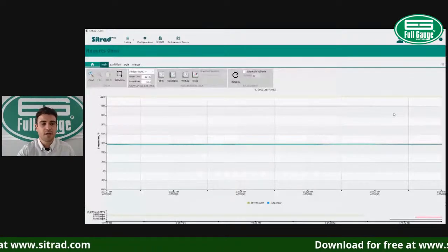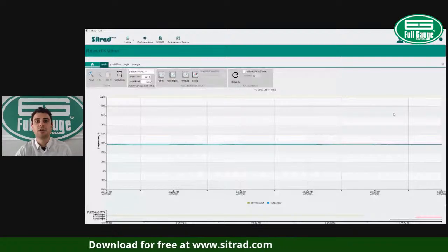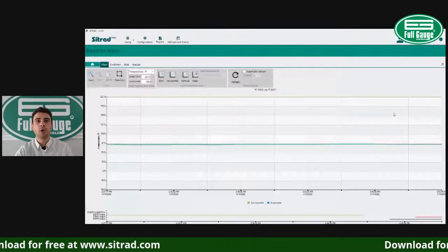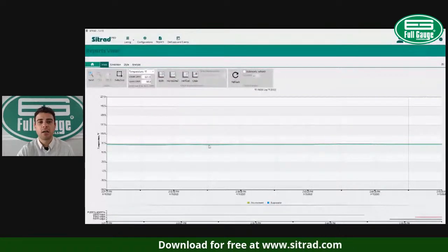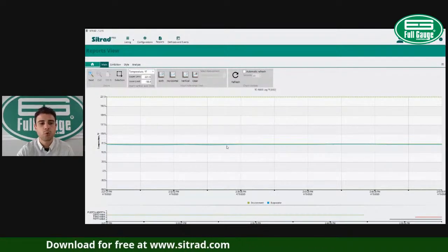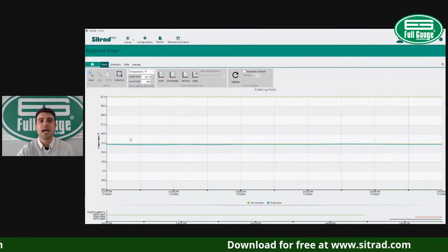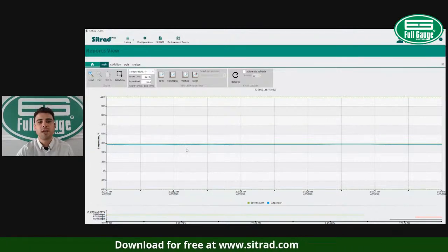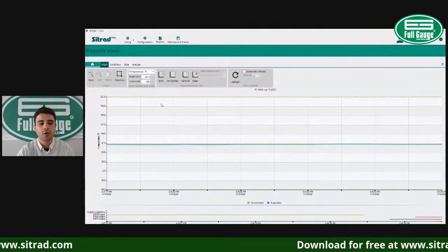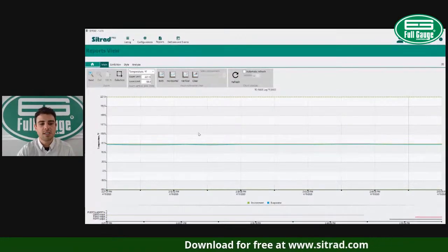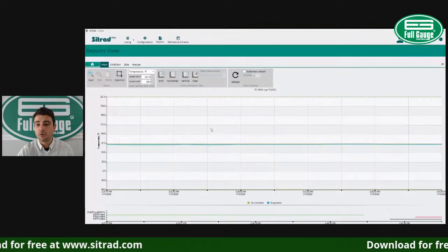And here we have, so again, this is a demo site, so there is no real equipment connected to it. That's why both temperatures are very close to one another. But if you had a real site installation, you would have a graphic with a temperature difference between room and coil. And here we have our defrost cycle running constantly, and then the defrost cycle stopped.